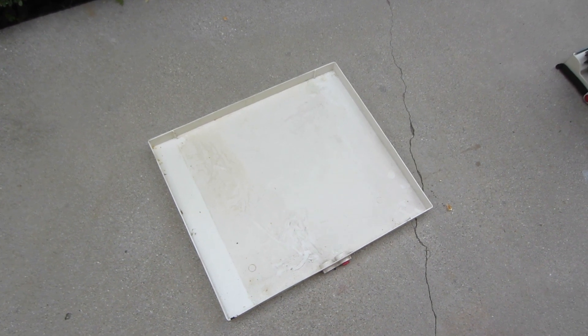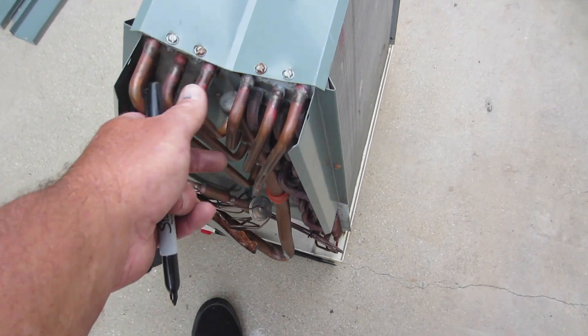Formicary corrosion — so you go up in the attic and the drain pan has an oil sheen across it. Basically, you're done.